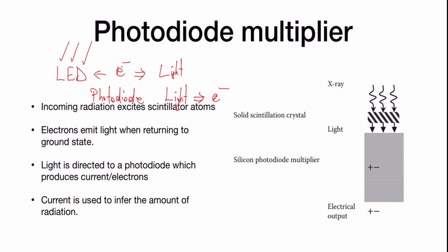So in this context, again, we would have a scintillator or a phosphorus substance, a substance that emits light whenever radiation hits it. Over here, I have a schematic of it. We have some input scintillator over here. Incoming radiation strikes it, but because this is easily excitable, when radiation hits it, it's going to produce light, or if you like, its electrons are excited, but then when the electrons de-excite, they produce light. This is what this light is. But then this light is directed toward a photodiode. Remember, a photodiode absorbs light and produces electrons.